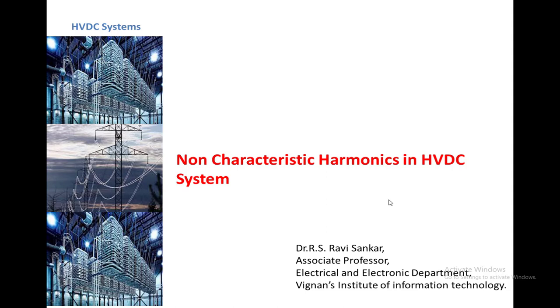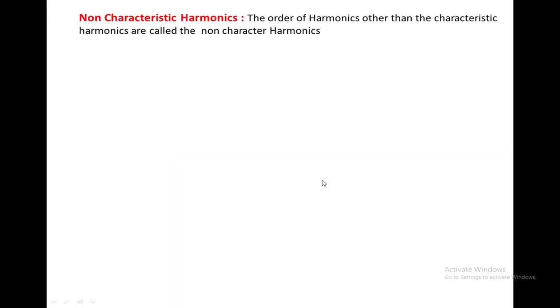Welcome to the class on non-characteristic harmonics in an HVDC system. In the last class we discussed characteristic harmonics in HVDC. Now we are going to see how non-characteristic harmonics are generated. The order of harmonics other than the characteristic harmonics are called non-characteristic harmonics, and these are generated in HVDC systems on both the AC side as well as the DC side.